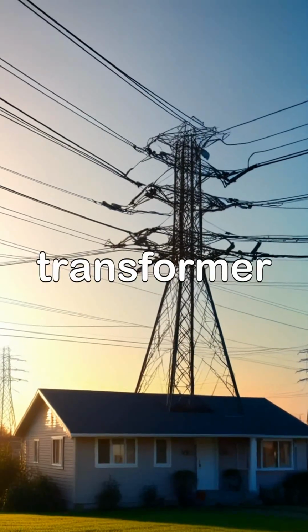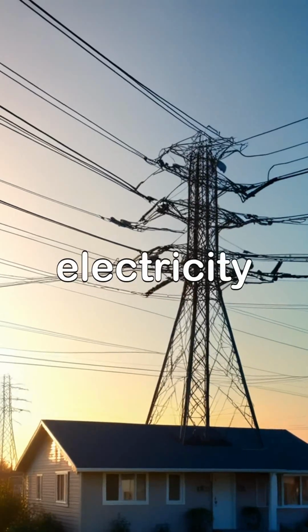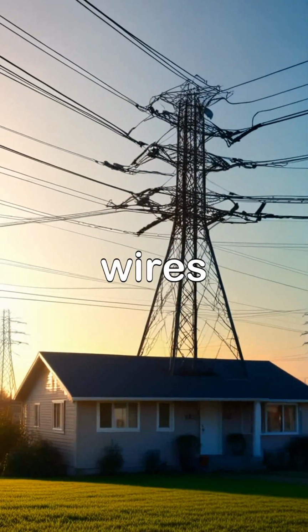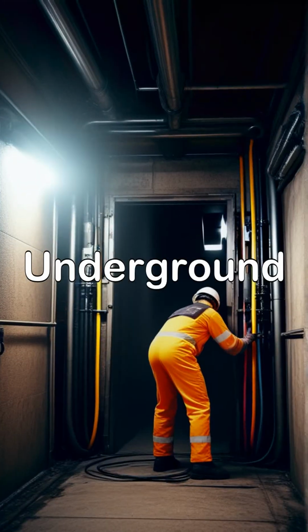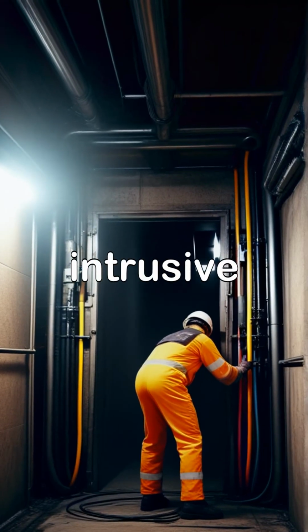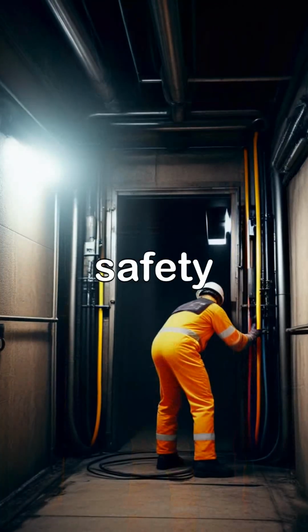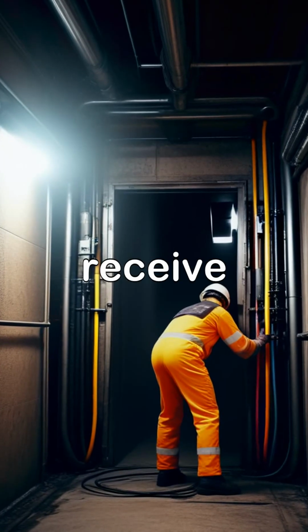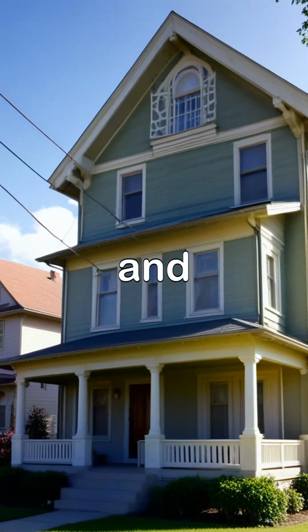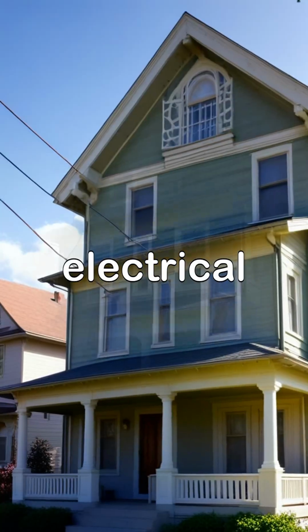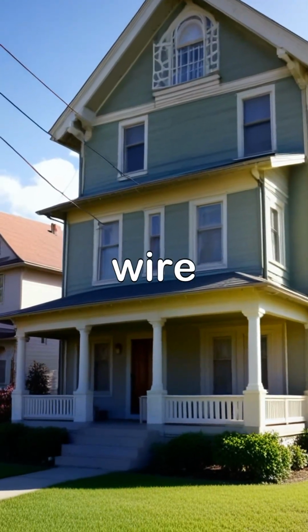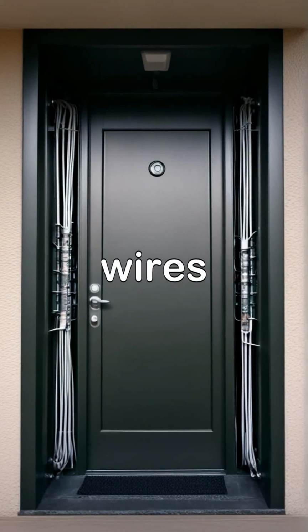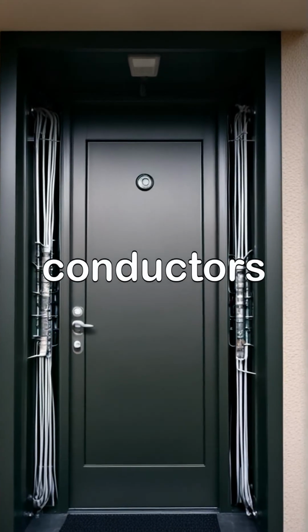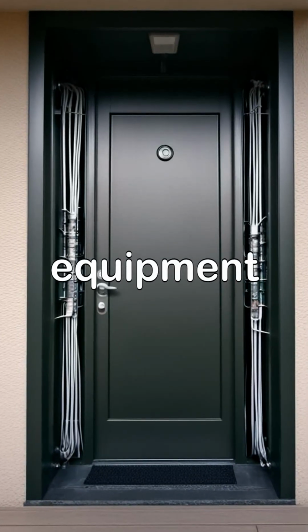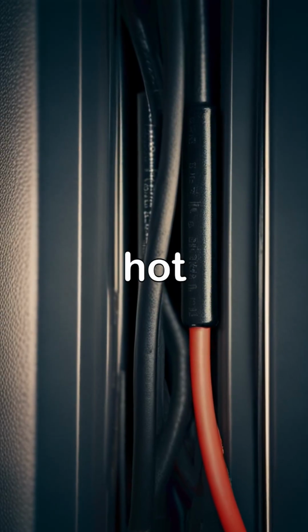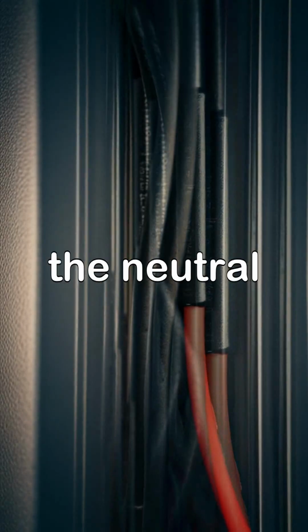Electricity in the home. From the transformer, the power company brings electricity into a home via overhead wires or underground cables. Underground service is aesthetically less intrusive, but there is no difference in the quality or safety of the electrical service you receive. Homes built after 1940 and pre-1940 homes that have had their electrical service modernized will have three-wire service. This means there are three wires called service entrance conductors connected to the service entrance equipment of the home. Two of these wires are hot, carrying current. The third one is the neutral conductor.